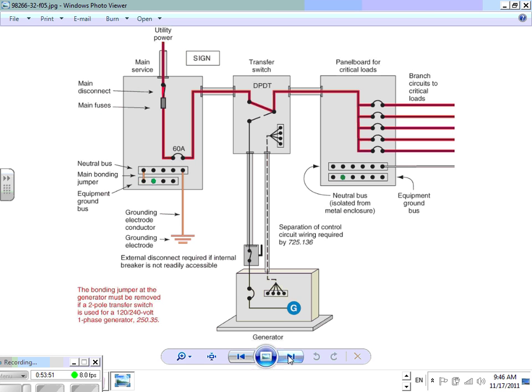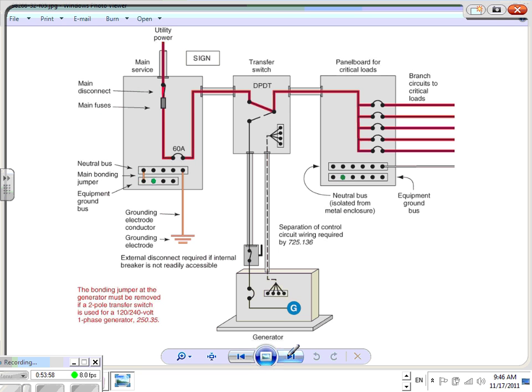If you look at this one, this is a permanently installed generator outdoors. You have a transfer switch. This is your main panel, the same arrangement. I have 60 amp coming through an EMT conduit, and I fit a transfer switch, which could be auto or manual. From there, I fit a sub panel, in this case a 60 amp sub panel.